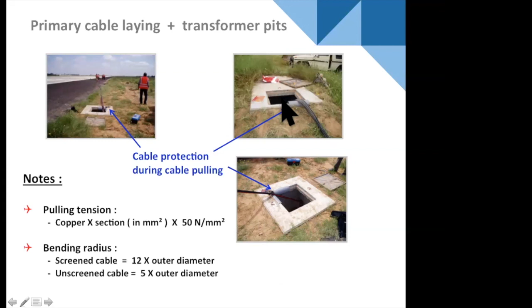And the bending allowance depends on whether it's screened cable or unscreened cable. Screened cable is 12 times the outer diameter, unscreened cable is 5 times. So that's the bending allowance. And we also need to protect cable across sharp edges of transformer pits. And here's one method of doing it. That is taking PVC piping, a very good way of doing it, cutting it in half and laying it over so that the cable runs over PVC. A pretty good way of doing it.